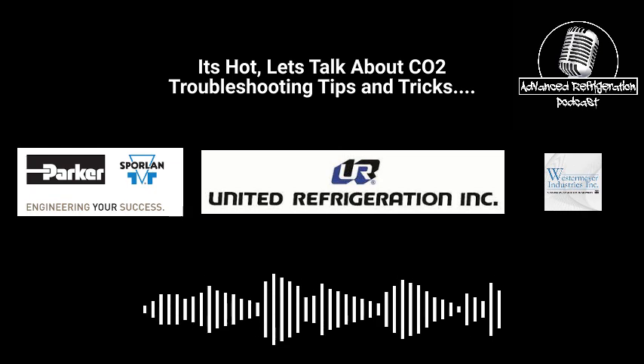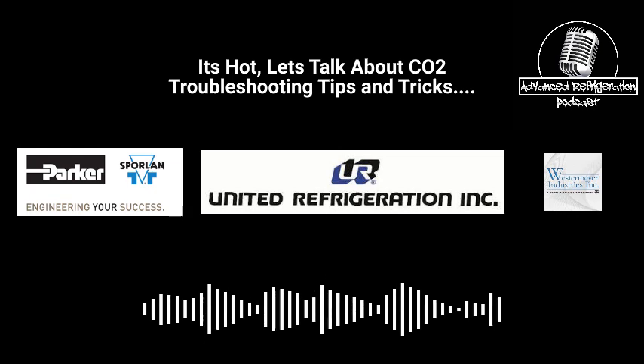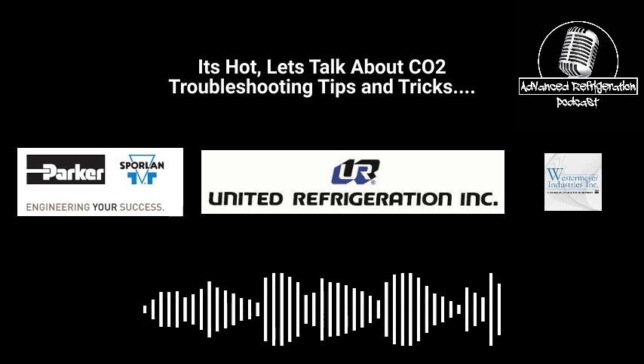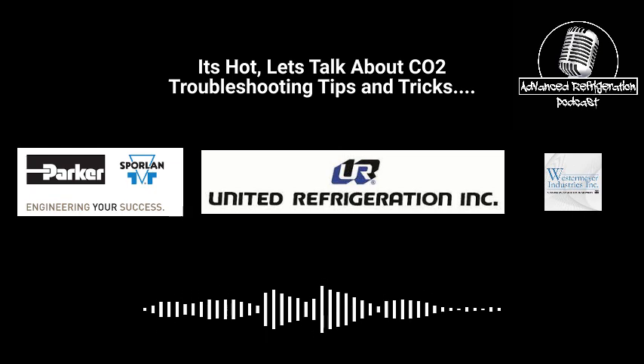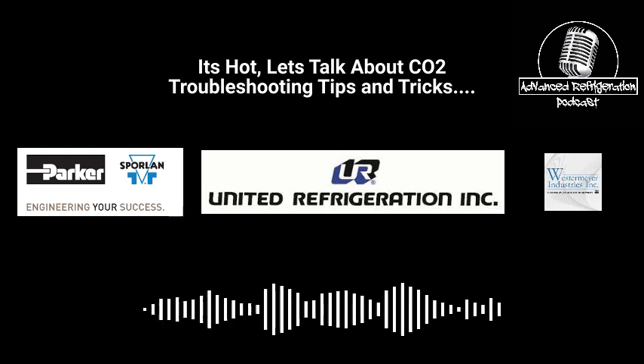That and then temp sensors on both sides of the valve. That would make a lot of sense, because you'd be able to sense the pressure drop or the phase change. Yes, you'd be getting more of a phase change out of there, and then it would be more graphable. Usually on these racks, your suction temp sensor is on the entering side of the accumulator.